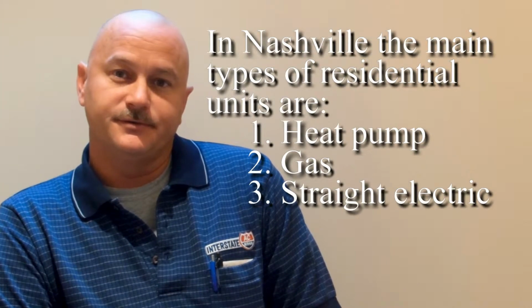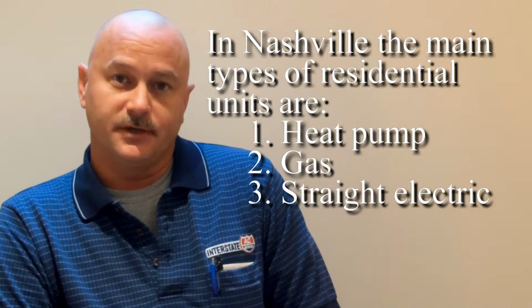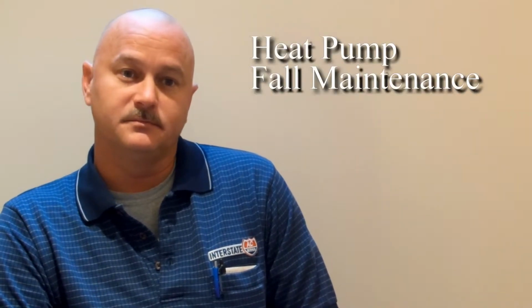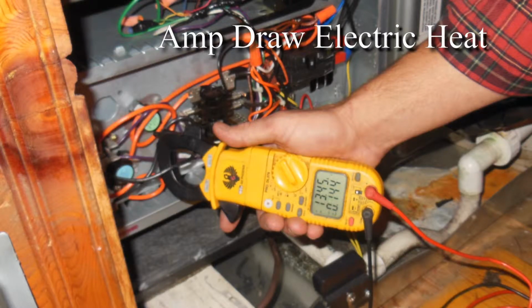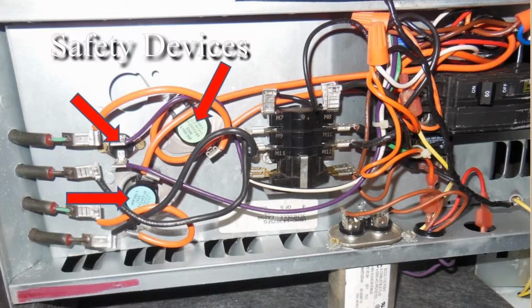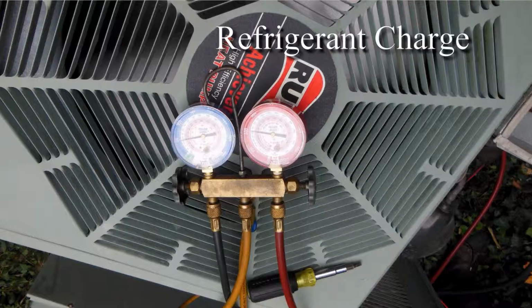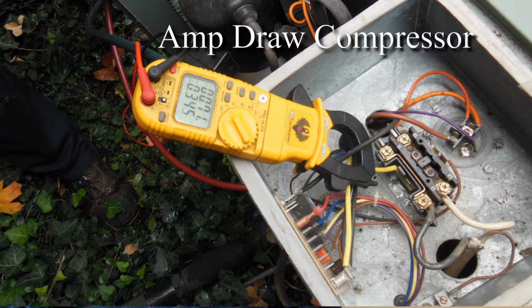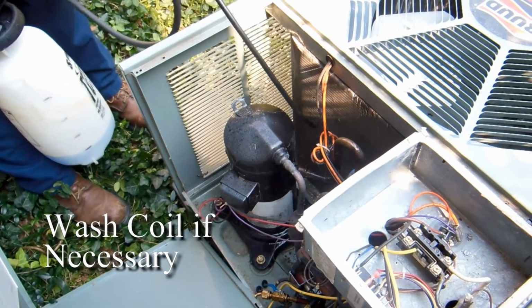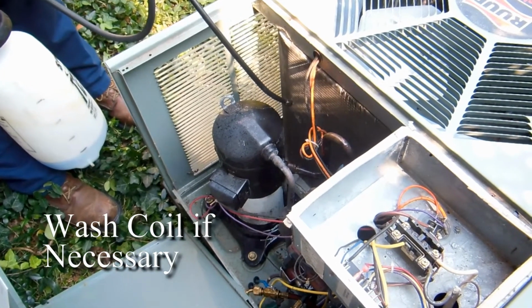Main types of residential units are heat pump, gas, and straight electric. A heat pump, we're going to check the amp draw on the electric heat to make sure that it is working and functioning properly, that all the safeties on the electric heat are working properly, and we're going to check the charge on the system to make sure that the refrigerant level is where it should be. Check the amp draws on the compressor, check the amp draws on the blower, the condenser fan motor, and we will wash the condenser coil if necessary.